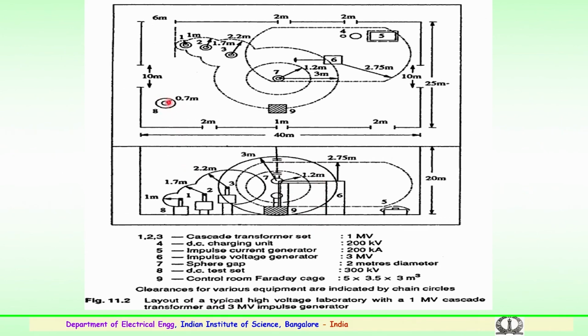So, the DC test setup is again kept at a corner with a clearance so as not to interfere with other equipment. You have a control room or a Faraday cage arrangement here. Again, the dimensions are mentioned here. So, typically you have an impulse voltage generator, a cascade transformer set of 3 units, an impulse generator, an impulse current generator, a DC set, and also the sphere gap arrangement. So, this typically gives the clearances of various equipment which are normally housed in a high voltage laboratory of 40 meters width by 25 meters or so and 20 meters. So, very important, and there could be higher voltage equipment which could be housed with higher clearances.